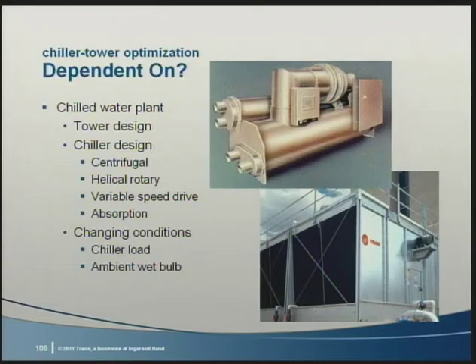Optimal control changes depending on the chiller type because each chiller reacts differently to the condenser temperature relief or lift. At each point in time, we can calculate the optimal temperature by looking at the chiller load, often done using temperature difference divided by the design temperature difference, and the ambient wet bulb temperature. So, what kind of savings are available?